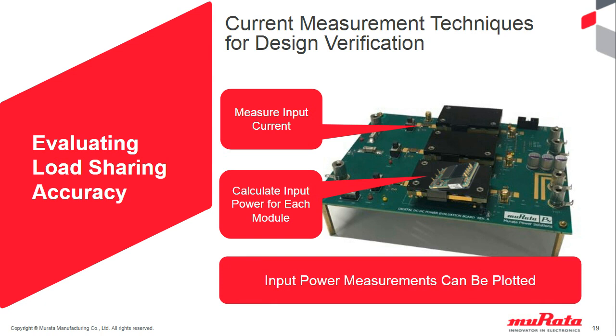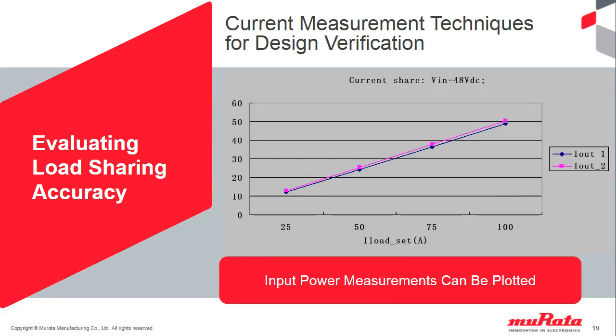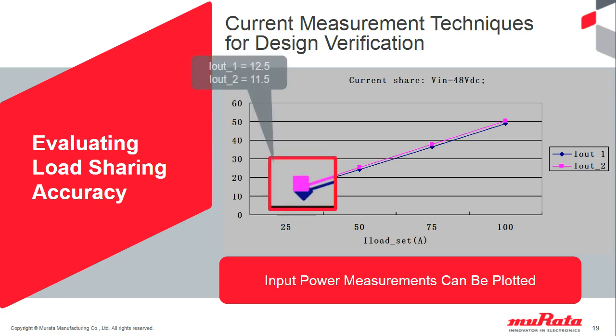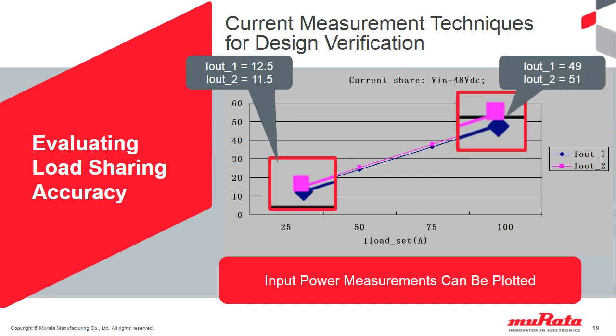So here's an example of these DSQ 600 watt modules under test conditions. As you can see, we test this from 25 amp load to 100 amp load. So down here, they're delivering about 12.5 amps apiece. Up here, they're delivering full power at 50 amps apiece. We've zoomed in here on the input. We see that we have about plus or minus half an amp at the lower end, and at the higher end, we see 49, 51, plus or minus 1 amp. So in this condition, this layout, we have very good load sharing between 2 modules. You can expect the same in your design following some of these basic guidelines.